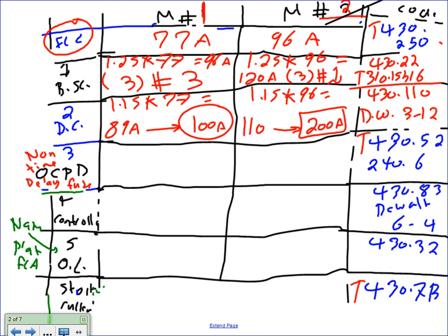Okay. Number 3 is the overcurrent protection device. For the overcurrent protection device, I need to specify what type. There is non-time delay fuse, there are dual element time delay fuse, there are instantaneous, and there is inverse time circuit breakers. So can you guys read my chicken scratch here that says non-time delay fuse? What am I using here? Non-time delay fuse. If you go to table 430.52, it will tell you, if you're using non-time delay fuse, your multiplier is 3.